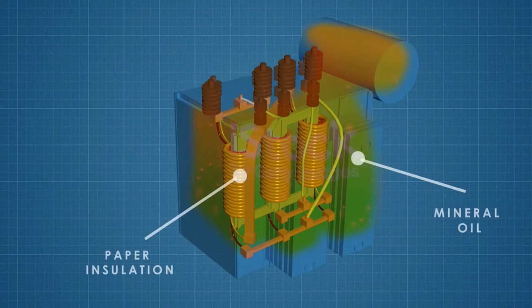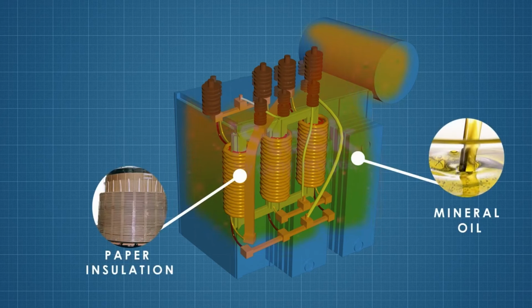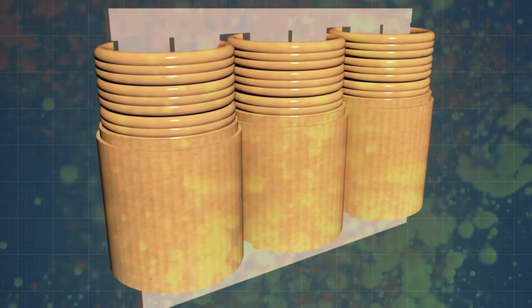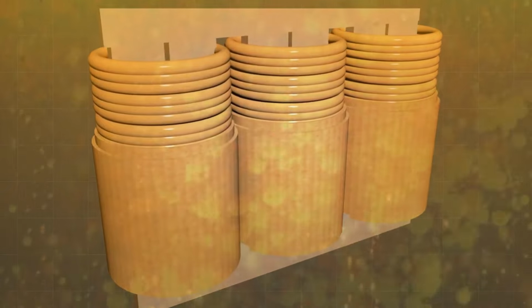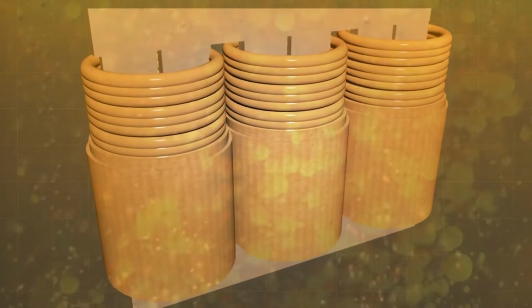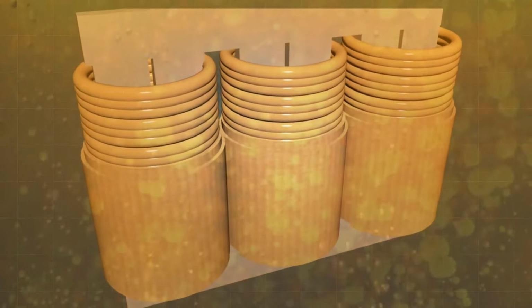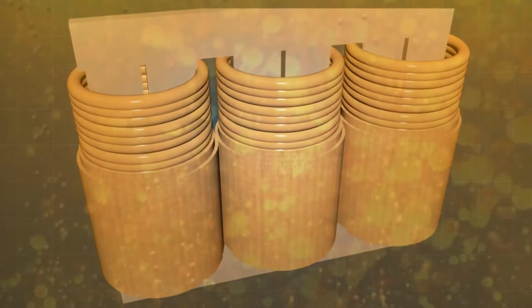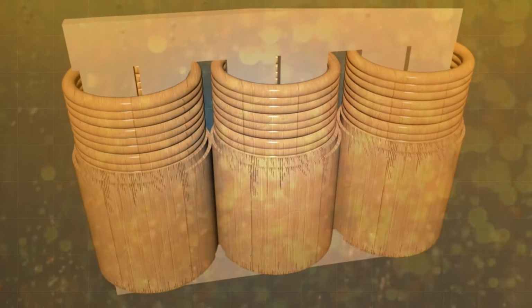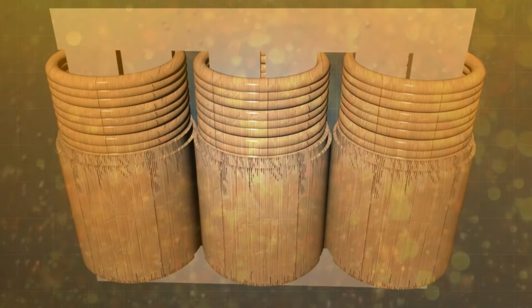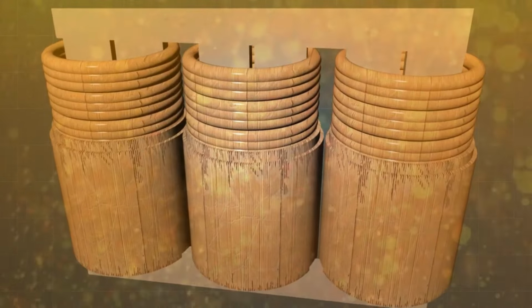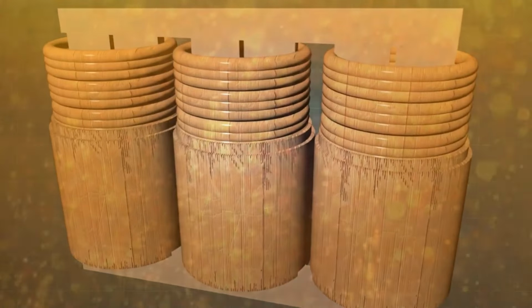Approximately 50% of transformer failures are related to the insulation system, which consists of mineral oil and cellulose-based insulation materials. This percentage is so high because transformer oil and insulation paper are subjected to various physical influences and chemical transformations: humidification, high temperature, oxidation, etc. These result in aging and degradation of the insulation, which becomes susceptible to electric breakdowns, causing premature transformer failure.